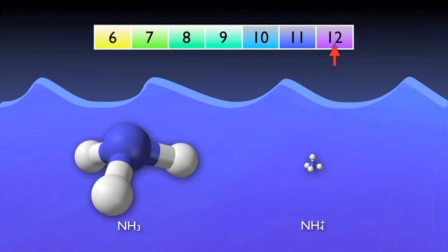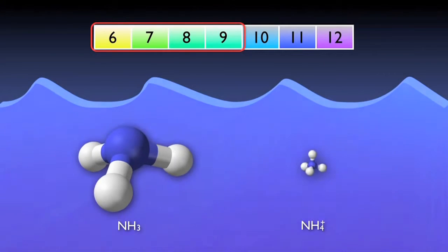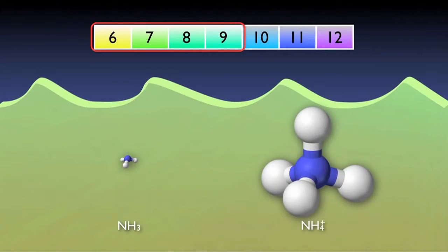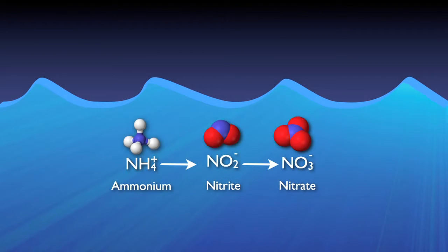Since wastewater typically ranges between a pH of 6 and 9, almost all of the ammonia will be in the ionic form. Since ammonia testing accounts for both forms, ionic and gaseous, it is not necessary to worry about each form separately. No bacteria is necessary for this conversion, it just happens. The next step in the process consists of converting ammonium to nitrite and then nitrate. This two-step process is usually lumped into one term, nitrification. This step is facilitated by a specialized autotrophic bacteria.